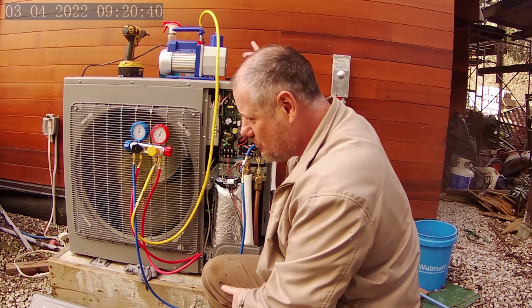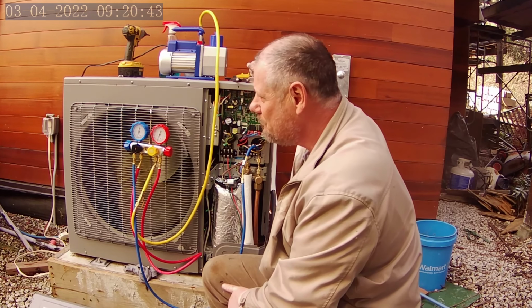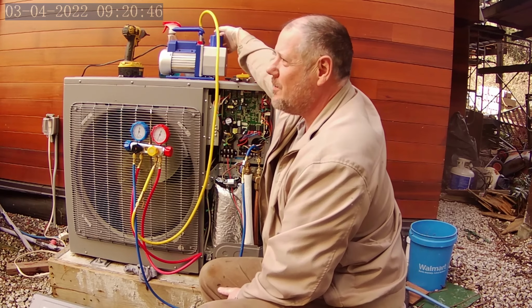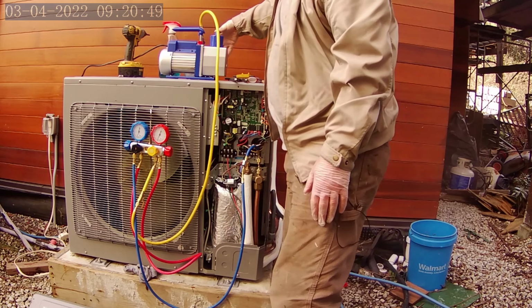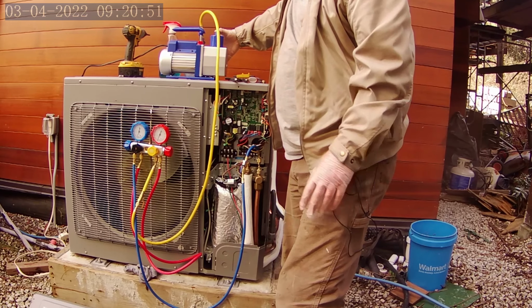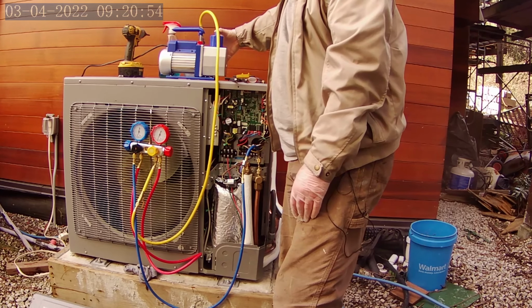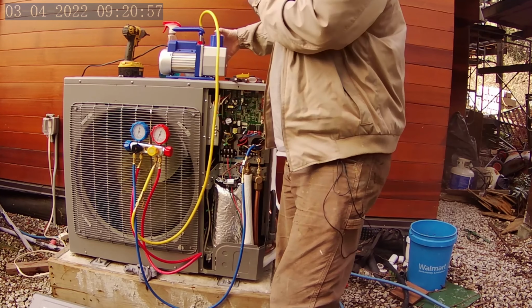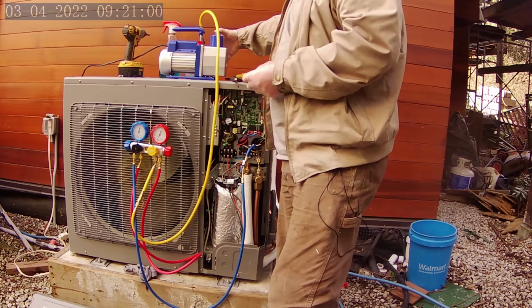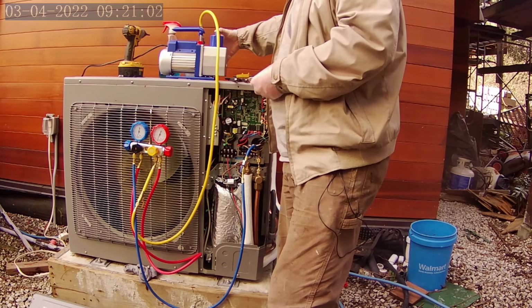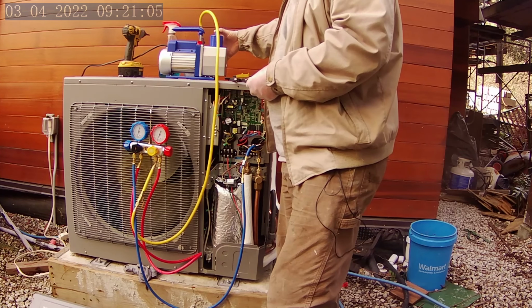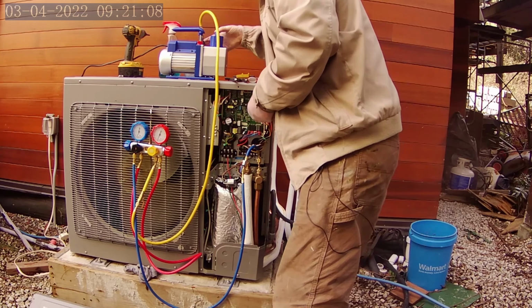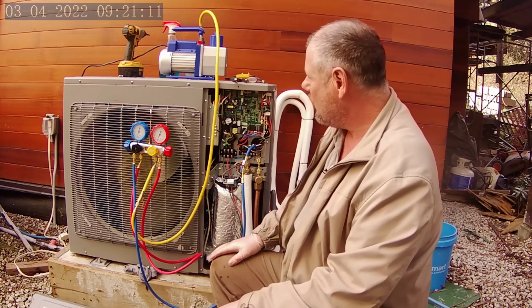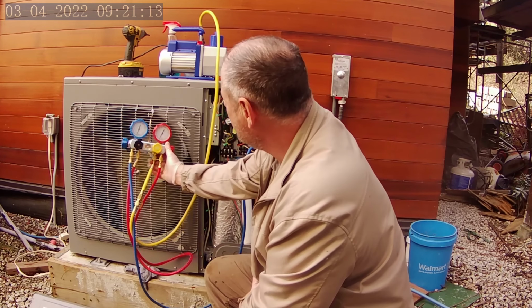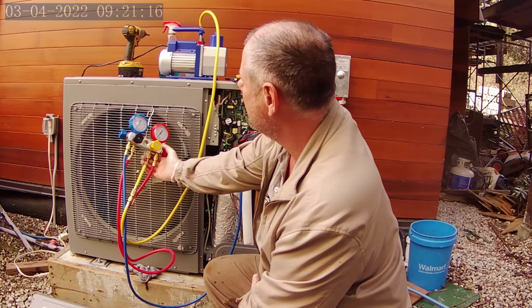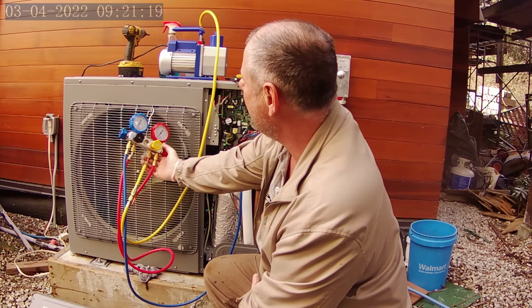Something else that I learned from one of these HVAC guys is a good tip: you put your finger on it for about 15 seconds, and then when you release it, you see whether or not any air comes out, whether or not there's any pressurization. And if you do, that means there's still quite a bit of volume of molecules that it's sucking out. And that's not really done anything at all. So we're getting pretty good. Actually, yeah, that's minus 30 now, or minus 29 and a half.